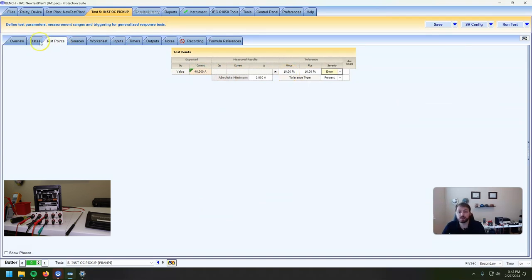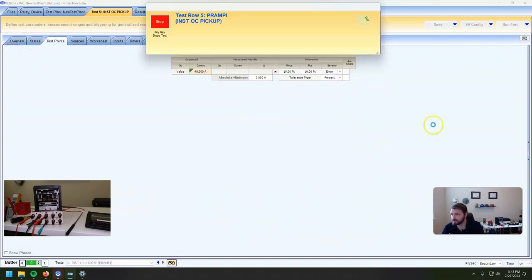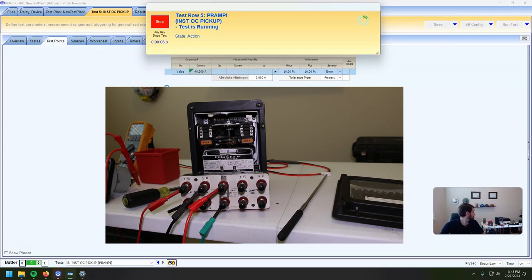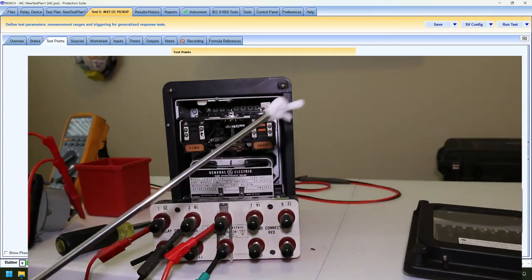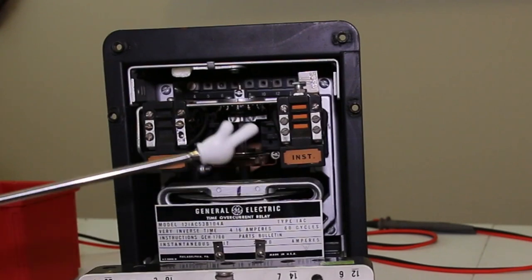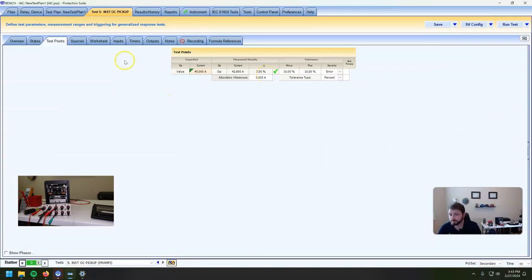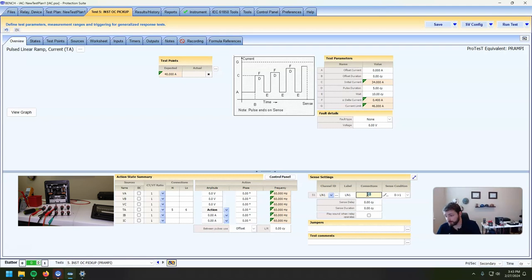This might be a little bit too much impedance for this output, but we'll see. It worked — we can see the flag drop on the instantaneous unit. Within 7%, we did 1% steps. We started outside our tolerance band, ramped up until we were inside our tolerance band, and then tripped. Everything works great. We used connections one to three. If we were wired up to the back of the case with the shorting bar in there, we could have done either one to two or one to three, because two and three are essentially one terminal.